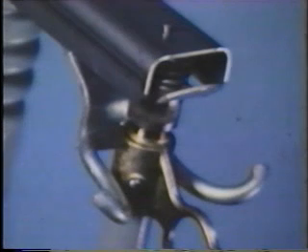Upon closing in, the top contact provides a socket-type cavity for latching the fuse holder. The unique engineered design of the upper contacts provides a smooth, self-aligning action during closing and prevents over-travel of the fuse holder, even when closing at an off-center angle.